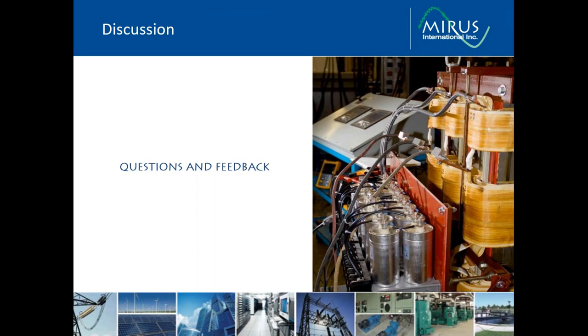So if you oversize a filter, then you can never get to the higher loading conditions, so you will never get to optimal current distortion performance. So again, that's why our recommendation is where you think you need to oversize because of environmental conditions, we would recommend the use of our extreme duty model. That then doesn't require oversizing.